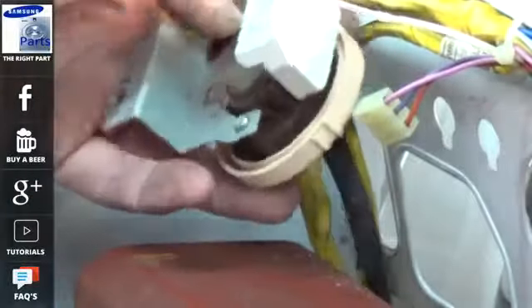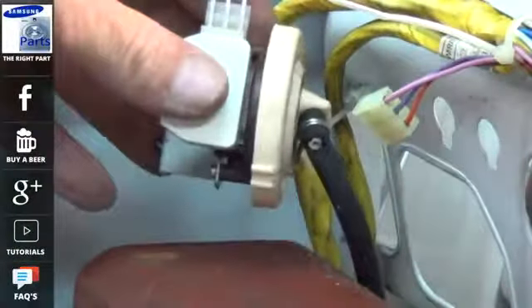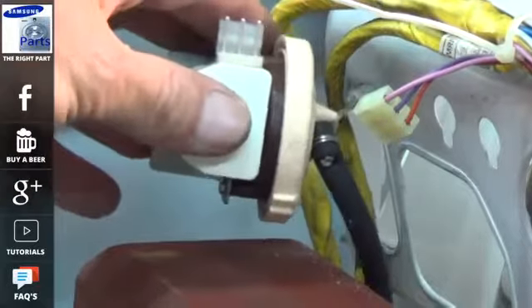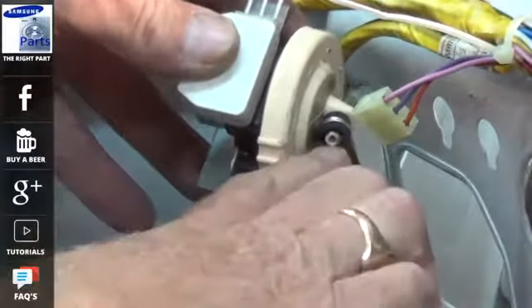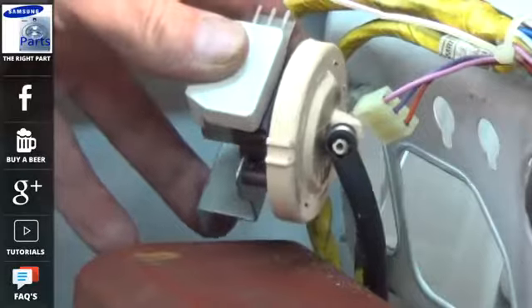Now the pressure switch may either have a bad connection on the electrical terminal, or this is a common fault. The pipe has actually chaffed on the connection to the pressure switch, as you can see here. I have had a few of these over the last few years.